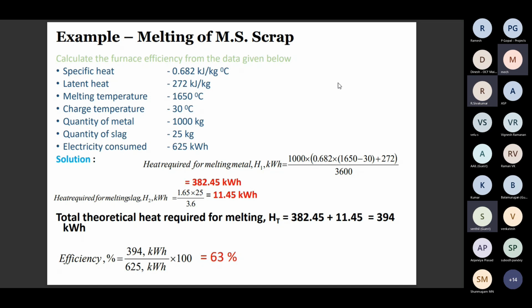Maybe you can collect it day-wise, and day-wise see how many melts you can take, and the entire value can be substituted, and the total electricity consumed, from the energy meter installed in the furnace, may be calculated for a day. For example, in a day you can take 20 heats. For the 20 heats, note how much metal you have melted, what is the average temperature range, and what is the average slag generated. By applying this you can calculate your own furnace efficiency. Okay, next one.